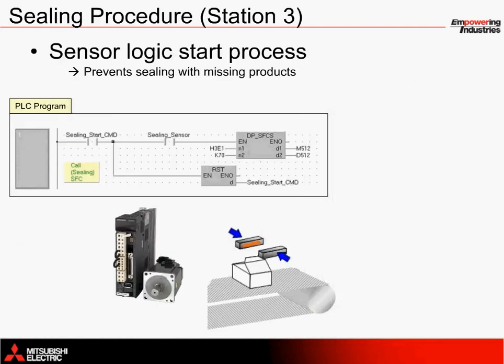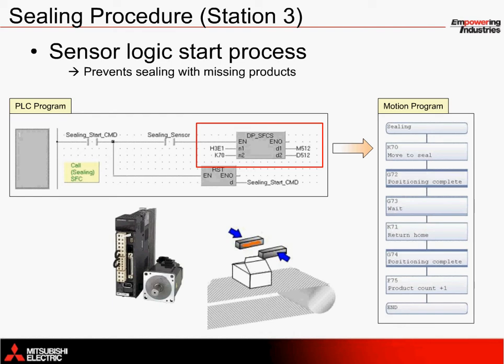Sealing begins with a DP-SFCS command from the structured ladder program in the PLC, which calls the motion program. You can see the DP-SFCS command calling motion program number 70. Condition requirements include a filling complete signal and a sealing station sensor on signal.